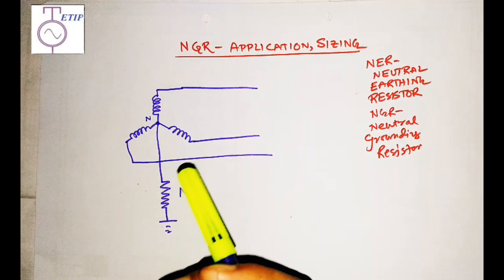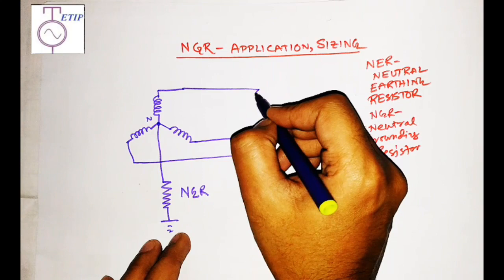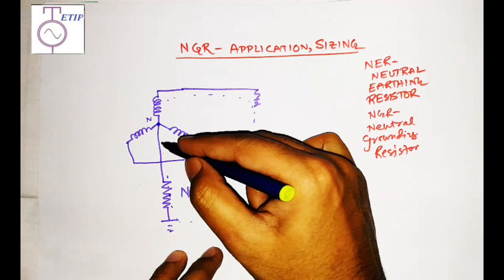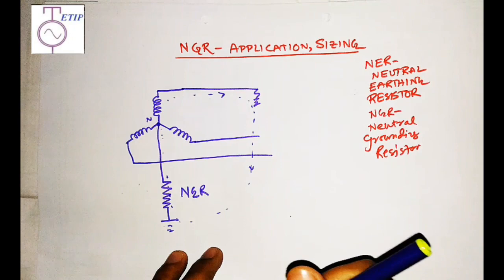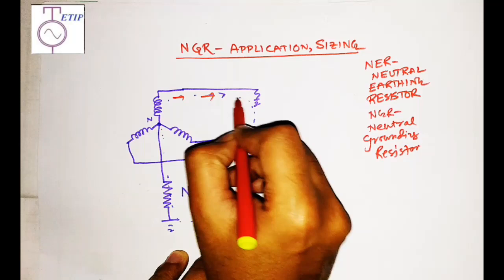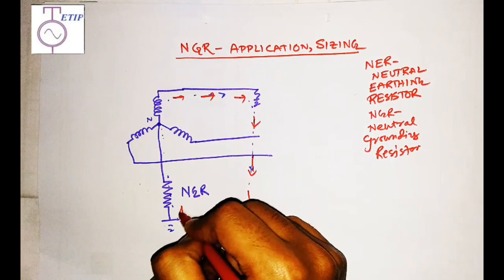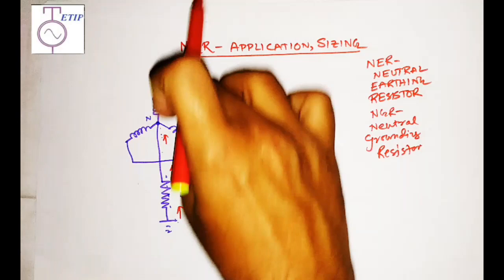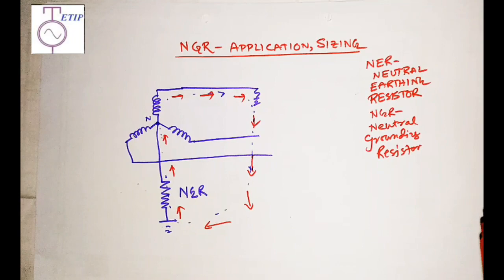For a transformer or alternator, if there is an earth fault on any phase, say this phase has faulted, then the earth fault current will flow from that point through earth, and from the neutral it will return to the source. If the neutral is solidly earthed, then the entire phase voltage will be imposed and a huge current will flow.